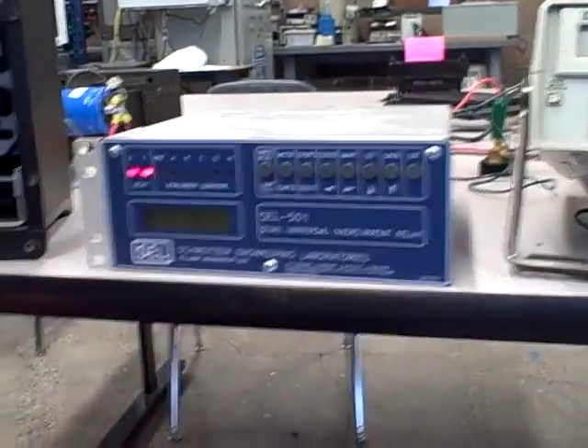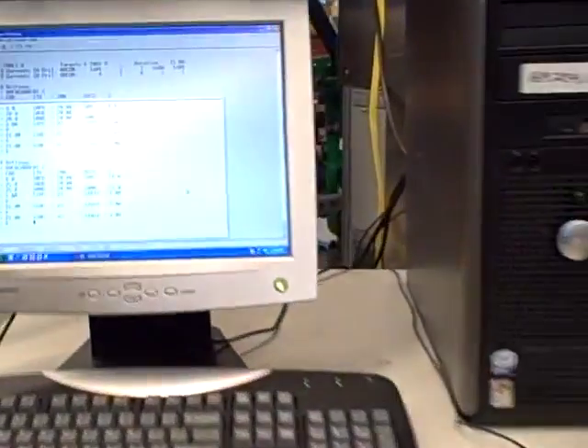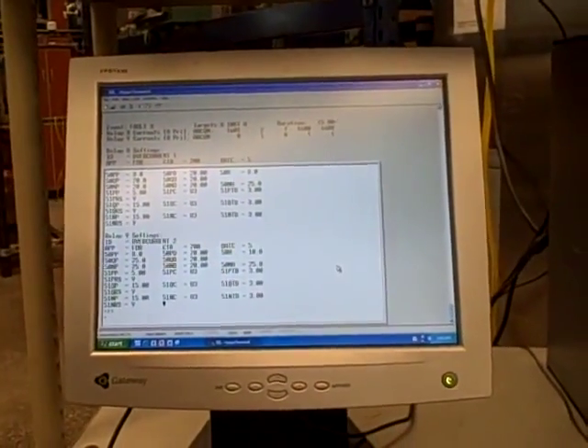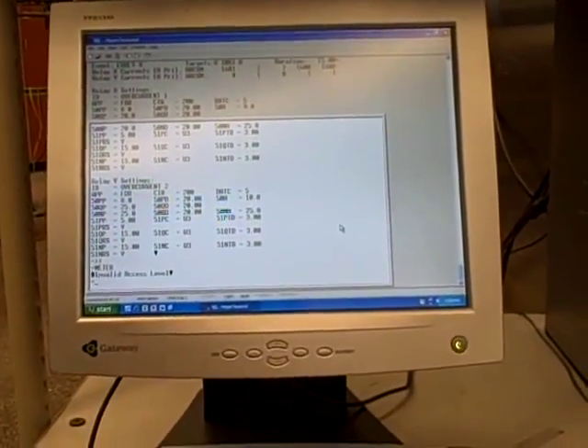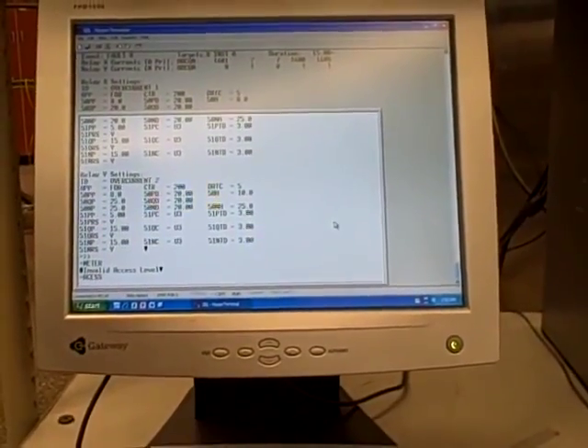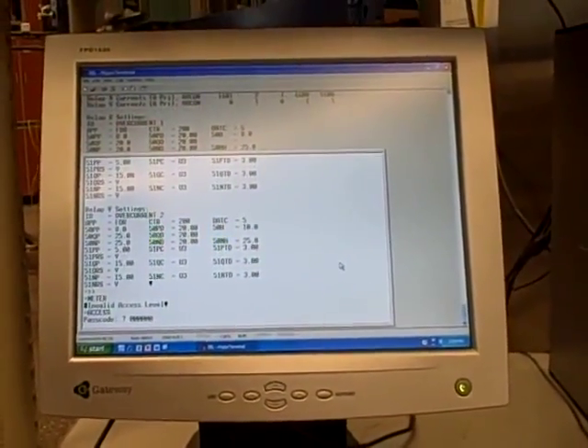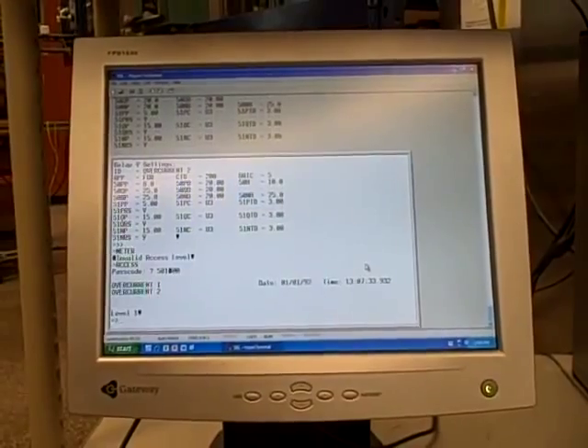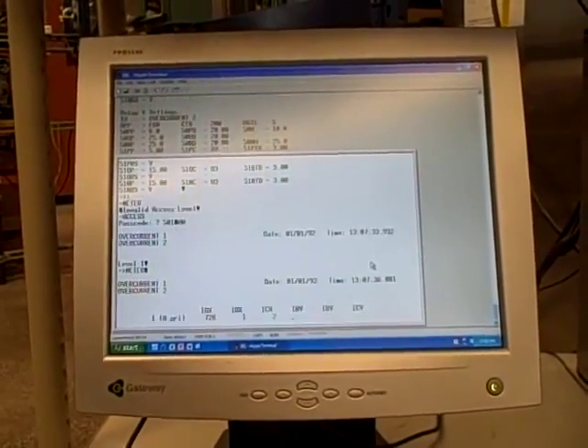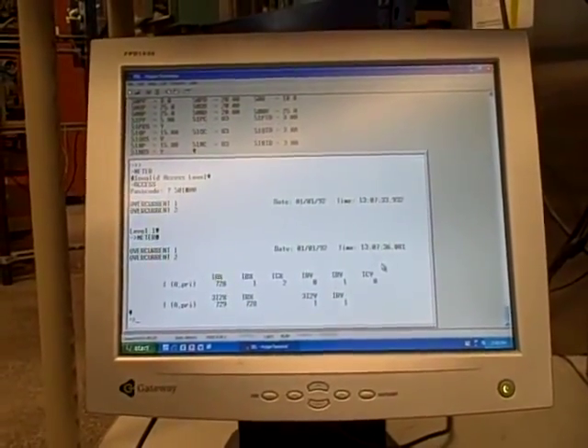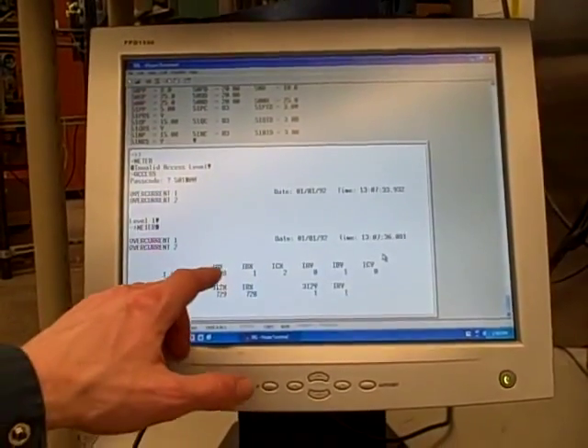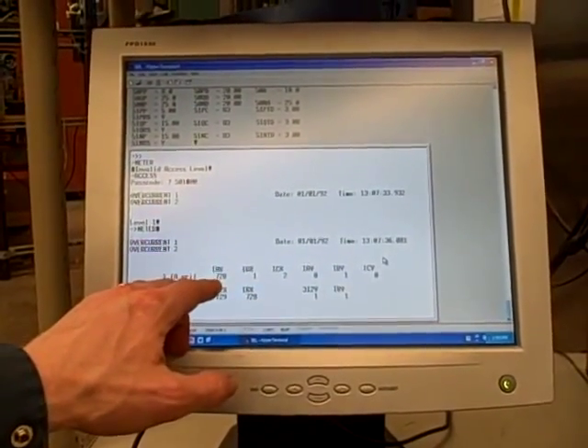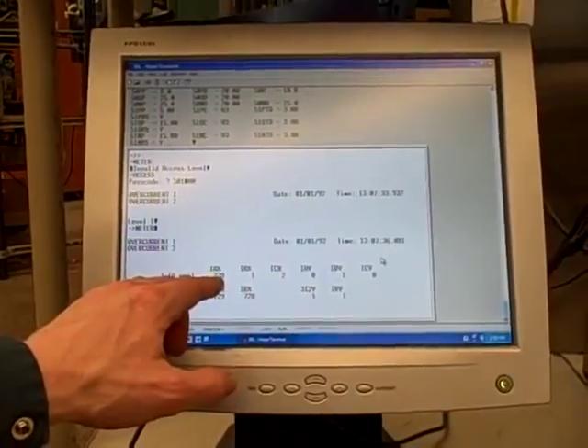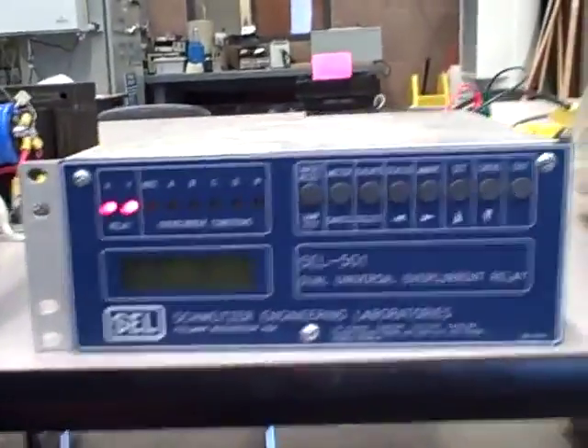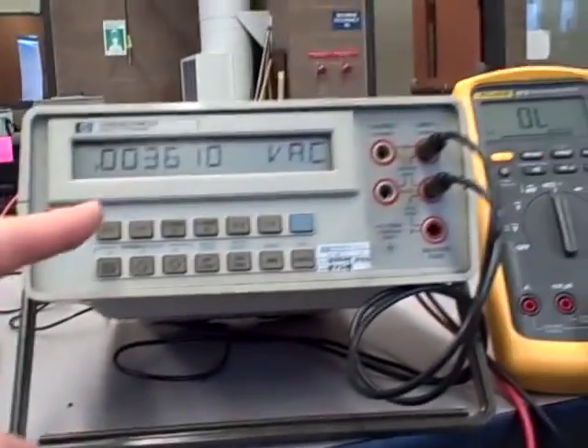So if I come over here, I see a computer monitor that's been connected to the relay, and if I type in the meter command, whoops, here we go. Type in access. I need to enter the password to get into that. If I type the meter command, I see what this relay thinks it's measuring. Right now, the current on A phase for relay X measures as 728 amps. If we go back to this, of course I'm not sending 728 amps into it, I'm sending in 3.6 amps.